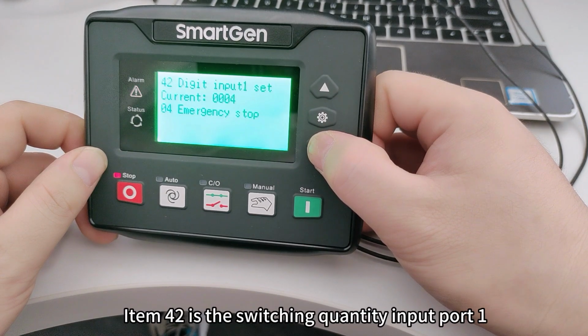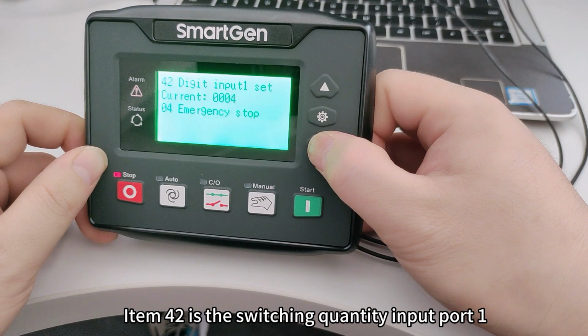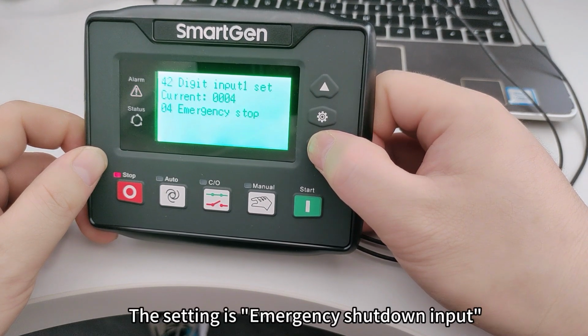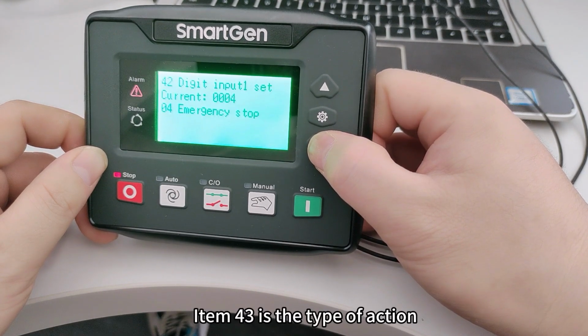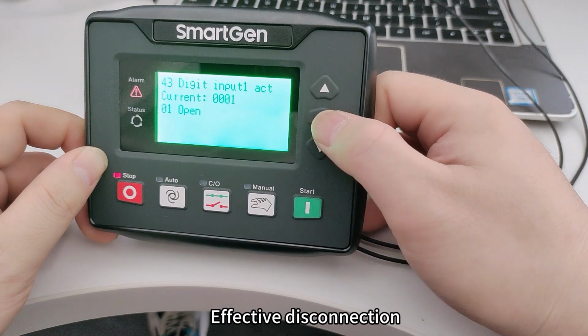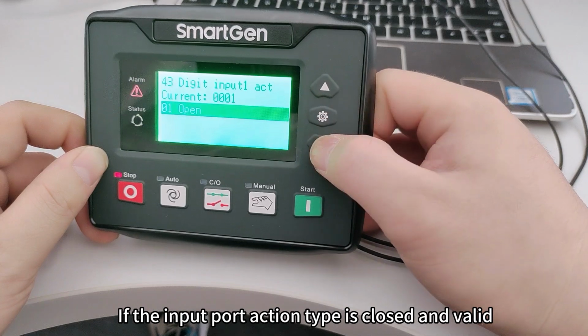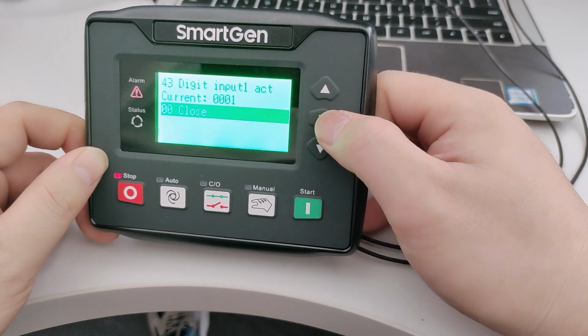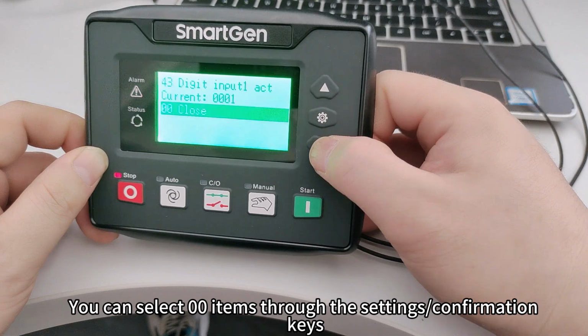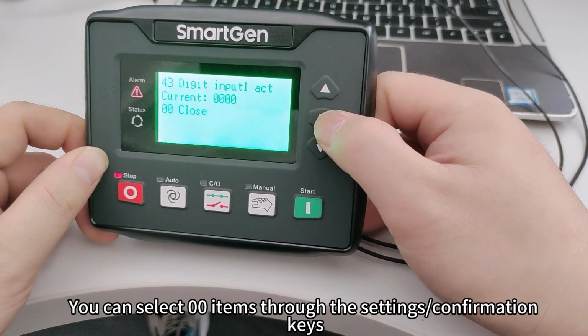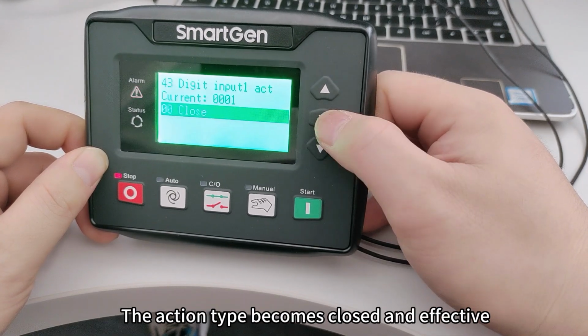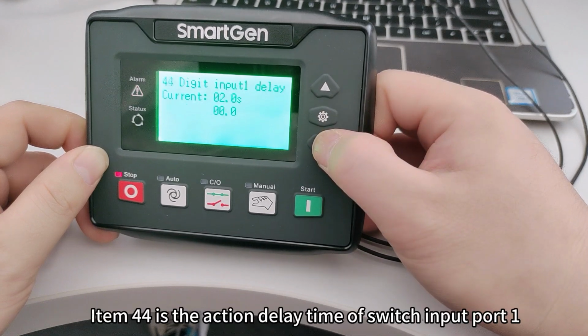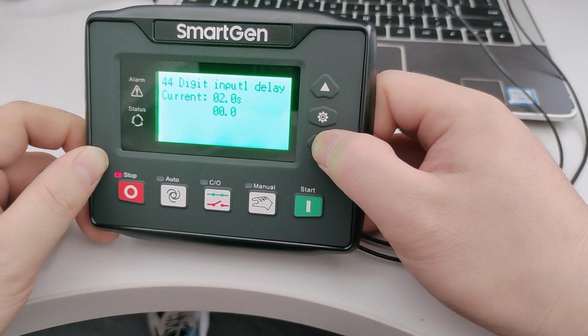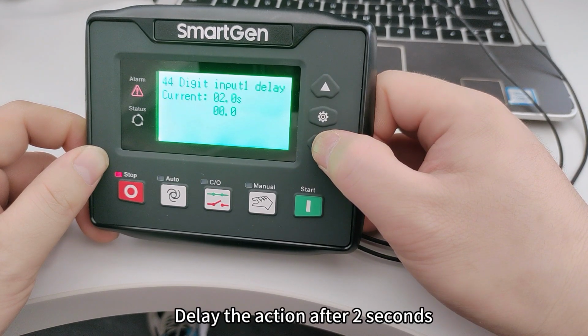Item 42 is the switching quantity input port 1. The setting is emergency shutdown input. Item 43 is the action type, closed or disconnected valid. If the input port action type is closed and valid, you can select item 00 through the Set Confirm keys. The action type becomes closed and effective. Item 44 is the action delay time of switch input port 1. Delay the action after 2 seconds.